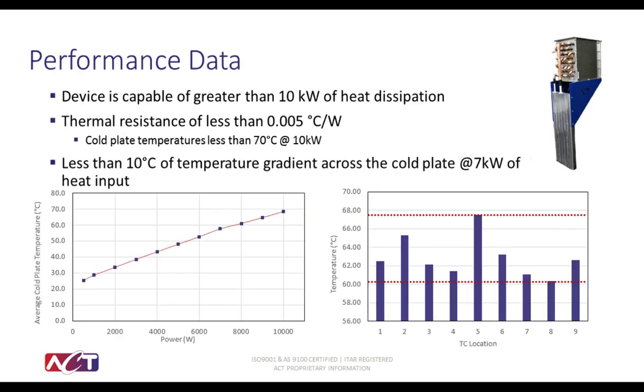Looking at the performance of these devices, ACT, again, generated the initial product offering for the power electronics market and has shown over 10 kilowatt worth of heat dissipation with a very low 0.005 degrees C per watt thermal resistance. As you can see on the chart on the left-hand side of this slide, your average cold plate temperature will increase with the amount of power transport through the system. For instance, if you're trying to move about 8,000 watts, we found that we can maintain a cold plate temperature of somewhere near 60 degrees C. And that will drop as you lower the amount of power carried by the system.